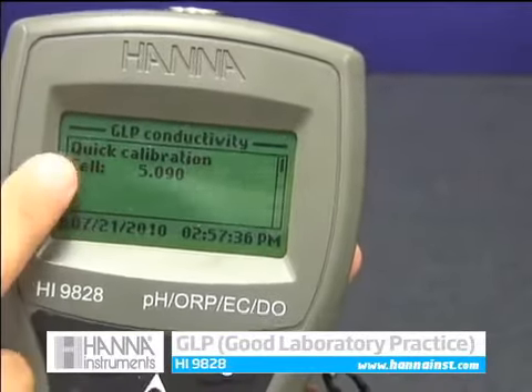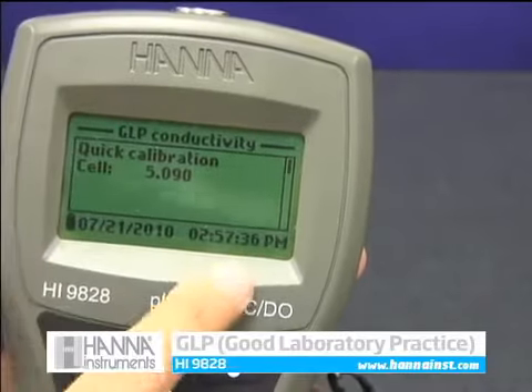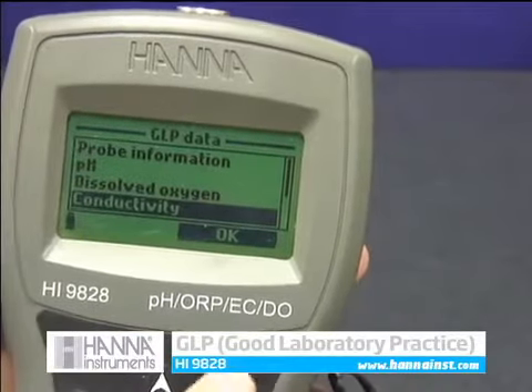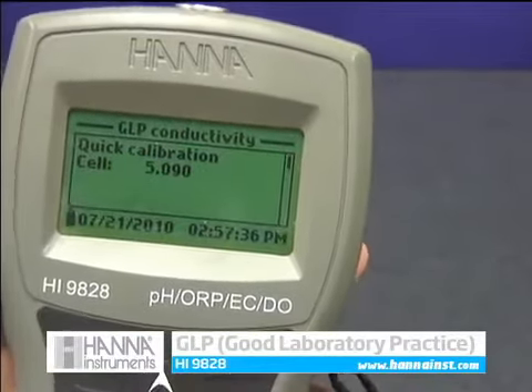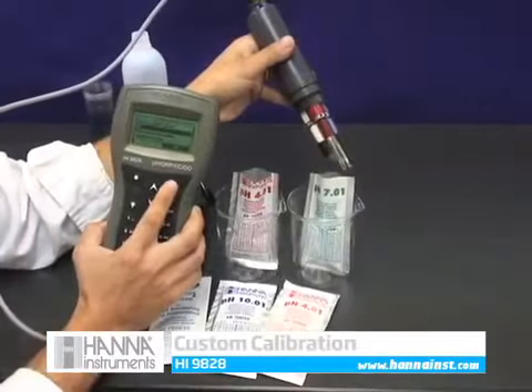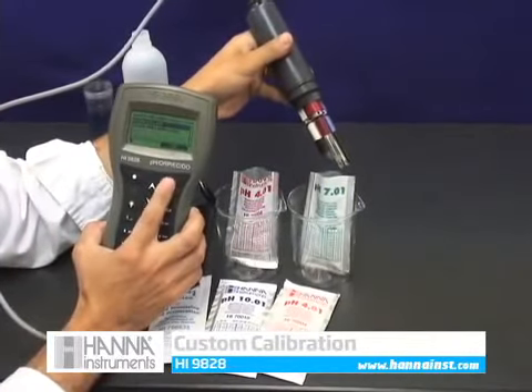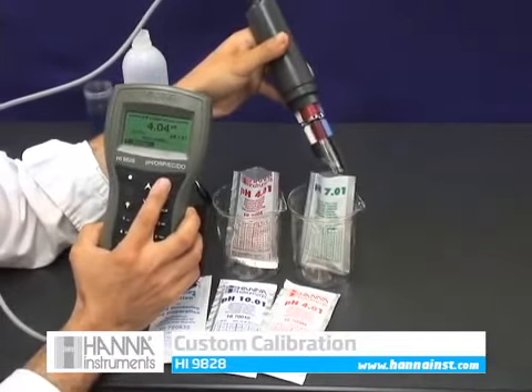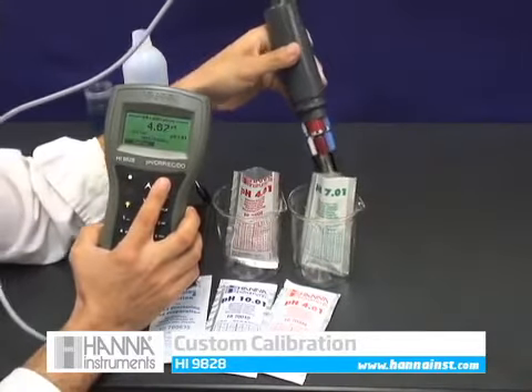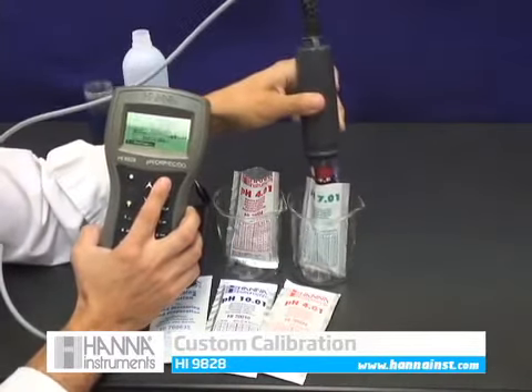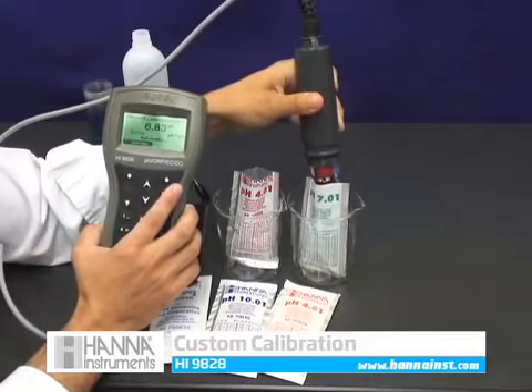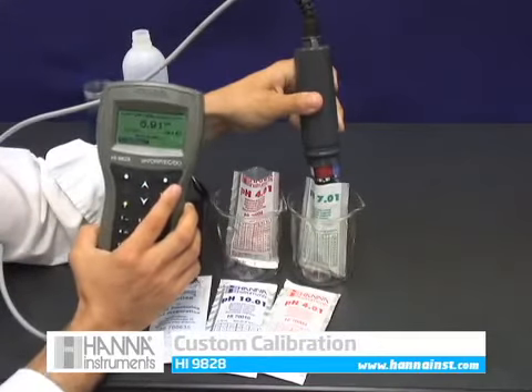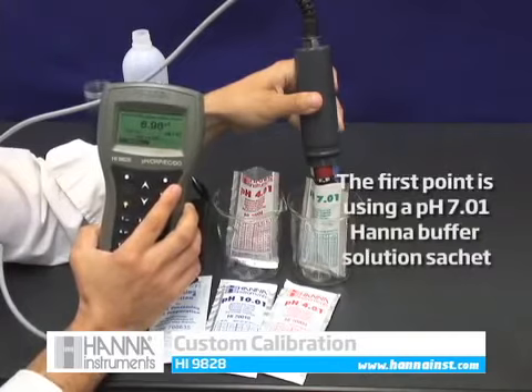As you can see here, Quick Calibration was the method, and the date and time clearly shows when this calibration was performed. Performing a custom calibration is easy with the HI9828. From the calibration menu, choose pH to enter the pH calibration mode. We'll perform our first calibration point of pH 7.01 by inserting the probe into the pH 7.01 buffer sachet.